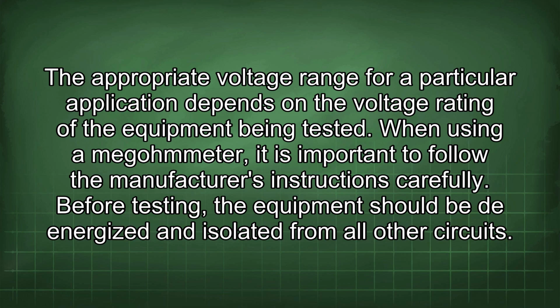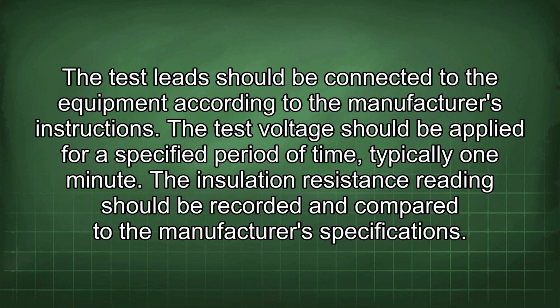When using a megohmmeter, it is important to follow the manufacturer's instructions carefully. Before testing, the equipment should be de-energized and isolated from all other circuits. The test lead should be connected to the equipment according to the manufacturer's instructions. The test voltage should be applied for a specified period of time, typically 1 minute. The insulation resistance reading should be recorded and compared to the manufacturer's specifications.